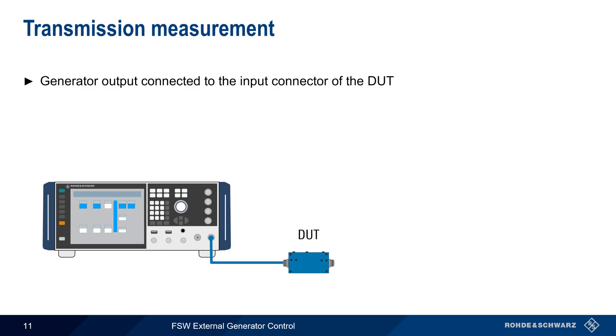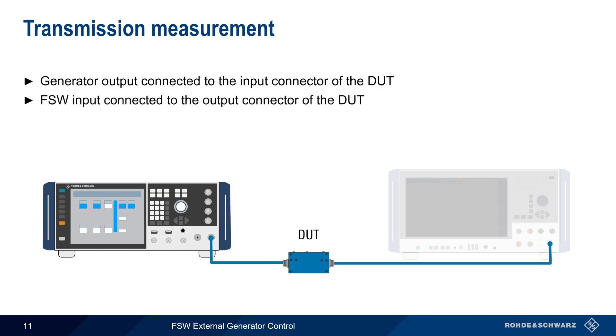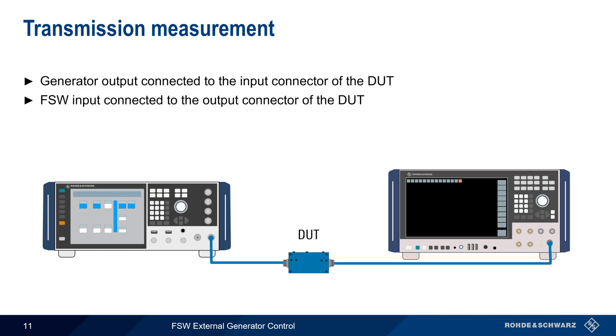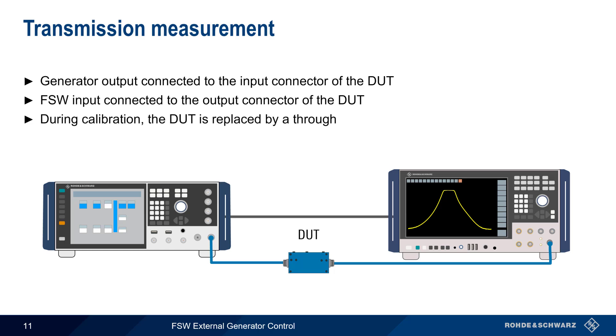Next we'll look at an example of a transmission measurement using a bandpass filter as a DUT. The generator output is connected to the input connector of the DUT, and the output of the DUT is connected to the RF input of the FSW. Once the connection is established, the FSW will display power versus frequency for the filter. Note that when this test setup is calibrated, the DUT is replaced by a through connector.